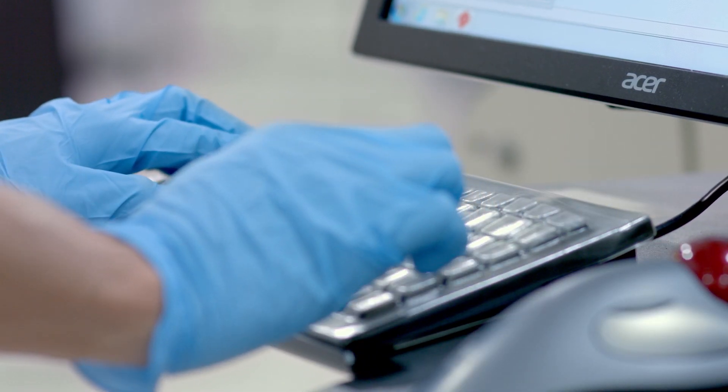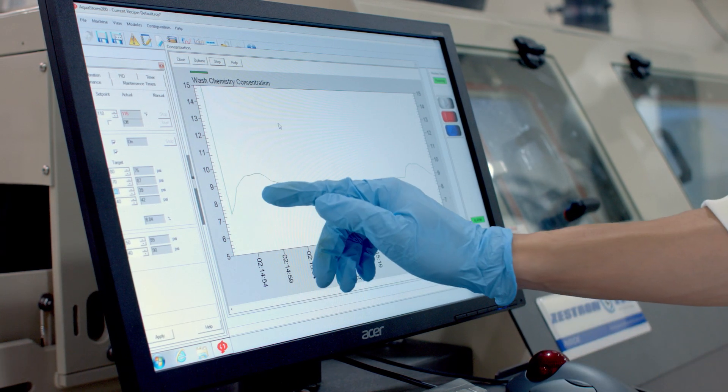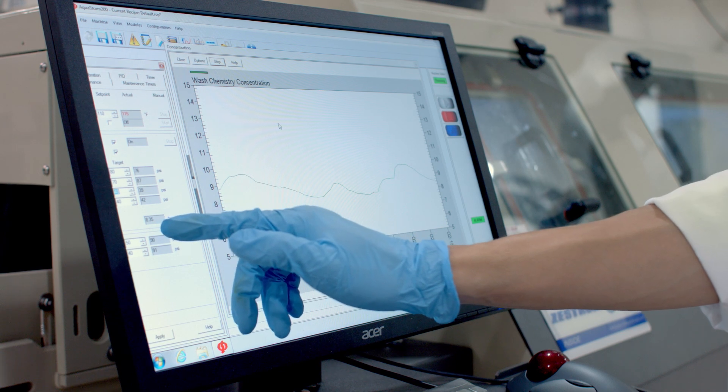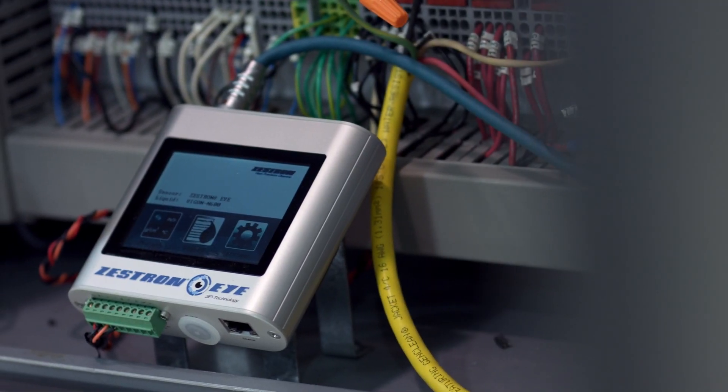The analog output allows transfer of the measured variables to an external device such as a PLC or desktop computer. This can be integrated onto most batch and inline cleaners and enables automated dosing for wash bath concentration management systems.